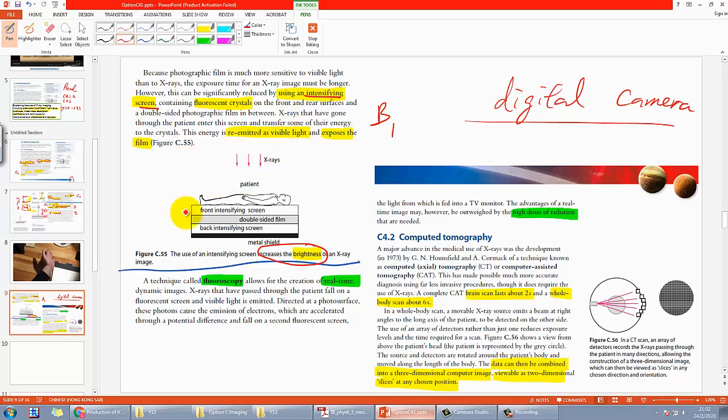And it's simply a physical property that the film is more sensitive to visible light, as you can see here. So this material is very interesting. What happens is that when X-ray shines on it, it scatters visible light. So basically it's more like an amplifier, because it changes the X-ray into visible light, and that visible light is simply more efficient in exposing the film underneath. So this helps you to increase the brightness.